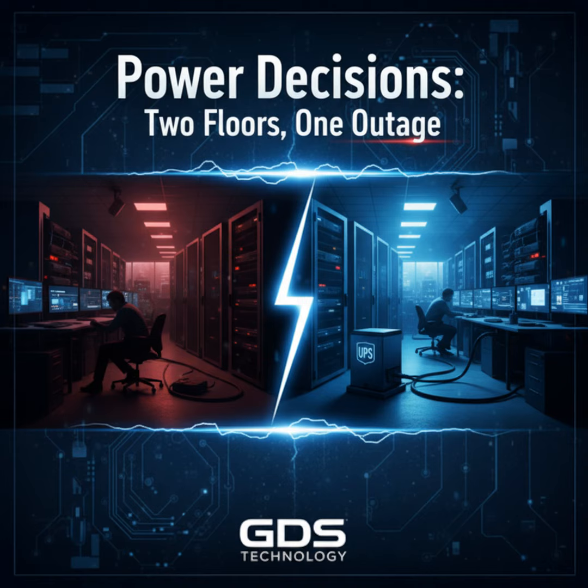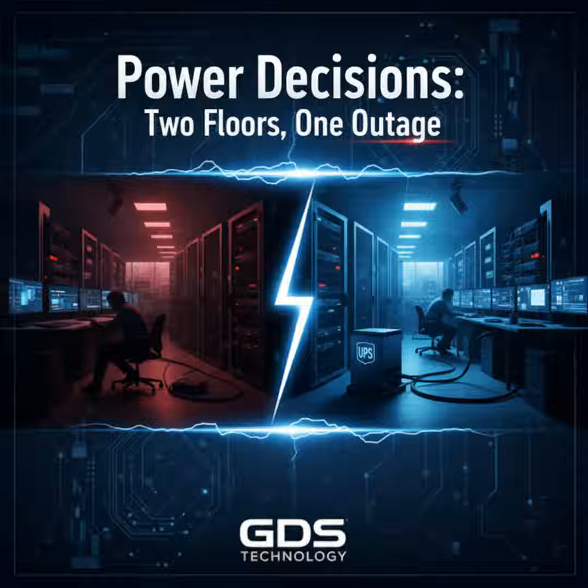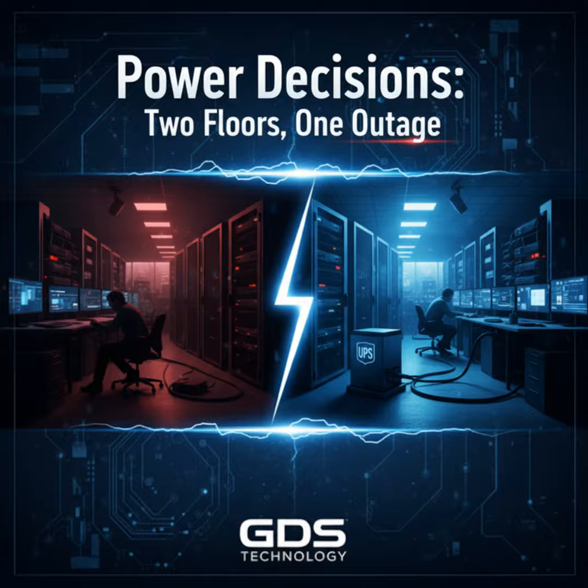Now, let's compare backup strategies without selling products. Tenant UPS versus building UPS is often framed as who pays and who maintains. A heuristic I use: if the load is exclusively tenant-owned and high variability in equipment is expected, tenant-managed UPS makes sense because the tenant will control upgrades. If the load supports shared services like access control, elevators, or shared Wi-Fi, then building-level UPS or centralized battery capacity is usually preferable to reduce operational surprises.